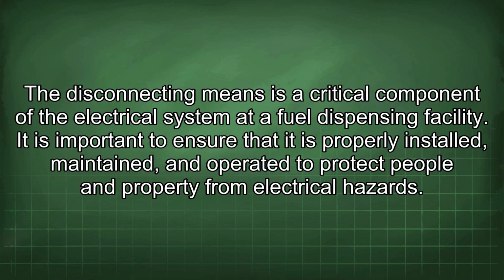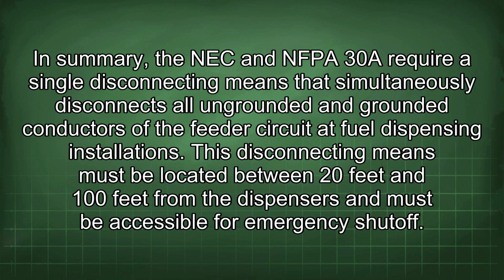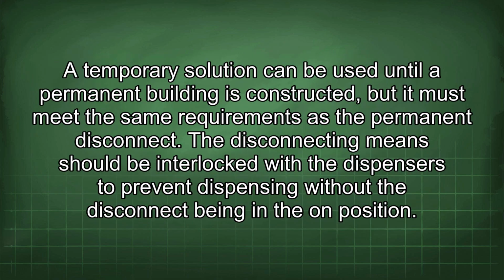The disconnecting means is a critical component of the electrical system at a fuel dispensing facility. It is important to ensure that it is properly installed, maintained, and operated to protect people and property from electrical hazards. In summary, the NEC and NFPA 30A require a single disconnecting means that simultaneously disconnects all ungrounded and grounded conductors of the feeder circuit at fuel dispensing installations. This disconnecting means must be located between 20 feet and 100 feet from the dispensers and must be accessible for emergency shutoff. A temporary solution can be used until a permanent building is constructed, but it must meet the same requirements as the permanent disconnect.